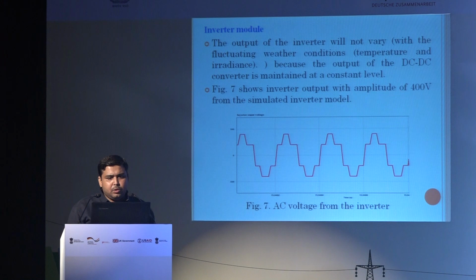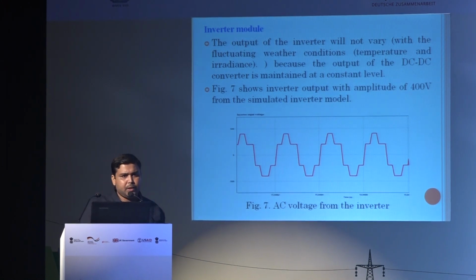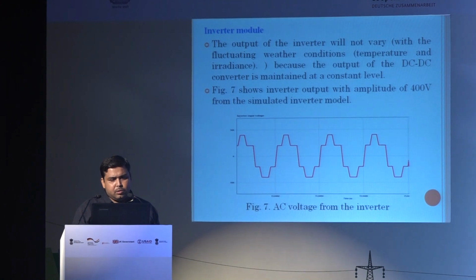Inverter module: the output of the inverter will not vary with weather conditions, because we have already applied the DC-DC converter and constant voltage control, which keeps the voltage constant. So the output of the inverter will not vary with temperature and irradiance, since the DC-DC converter is maintained at a constant level. In figure 7 you can see the AC voltage output from the inverter.